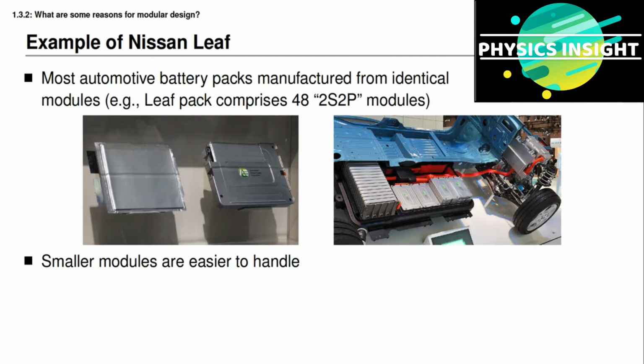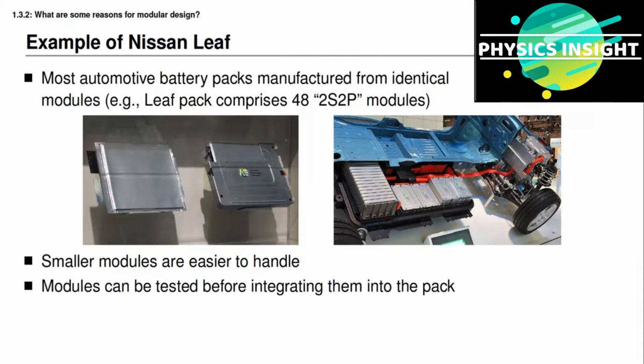In addition to safety reasons, there are some other reasons why building a battery pack from smaller modules can make sense. One is that the smaller modules are easier to handle by humans or by robots who are assembling the battery. The individual modules can be tested before integrating them into the pack, and if one module turns out to have a failed component, it's much less expensive to service that module than to service an entire battery pack.